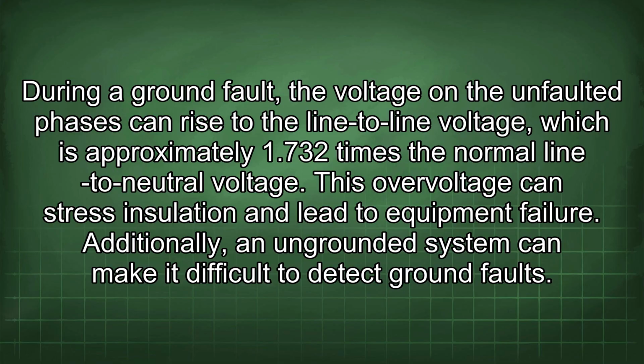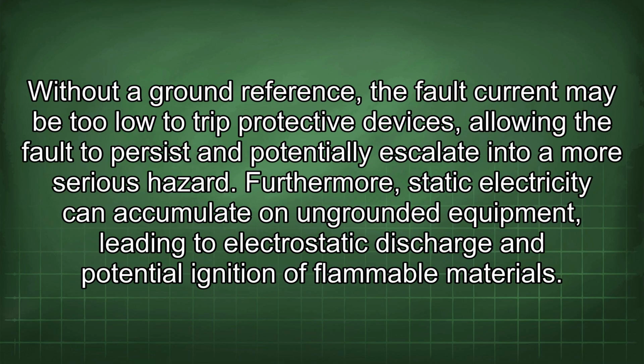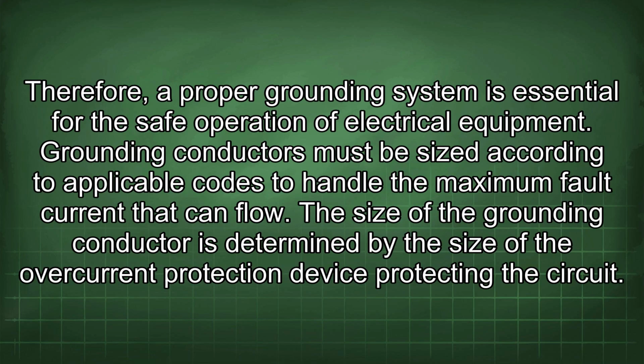Additionally, an ungrounded system can make it difficult to detect ground faults. Without a ground reference, the fault current may be too low to trip protective devices, allowing the fault to persist and potentially escalate into a more serious hazard. Furthermore, static electricity can accumulate on ungrounded equipment, leading to electrostatic discharge and potential ignition of flammable materials. Therefore, a proper grounding system is essential for the safe operation of electrical equipment.